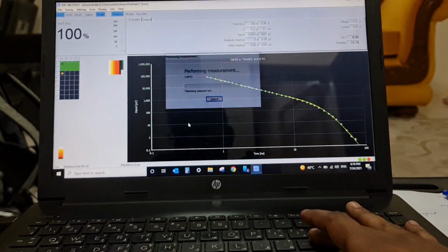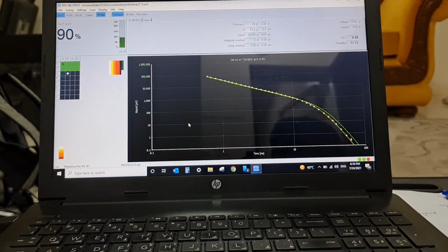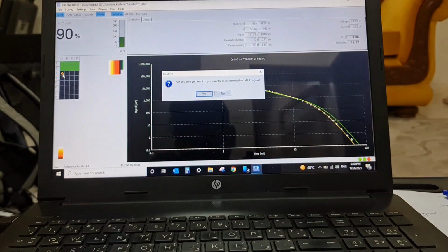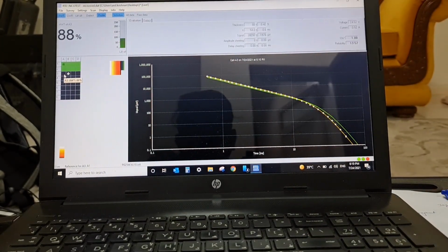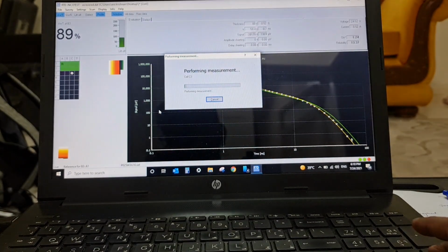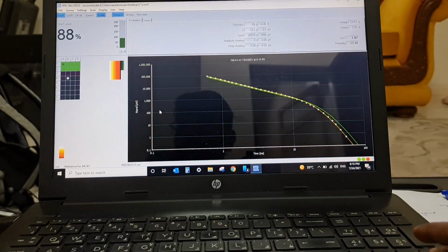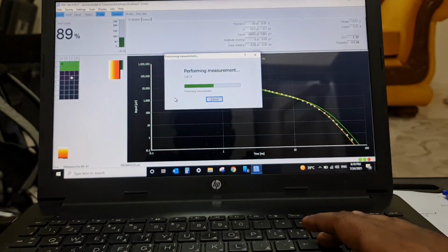On the second step, it was supposed to read 87.9%, which is an 11.1% reduction. That means 1 mm with the 9 mm thickness is 11.1%. So it is almost around 90, 88, which is very nearby. Because of some edge effect, if it is the edge it will have some variations, but still we managed to get 88 percent, which is nearly accurate.